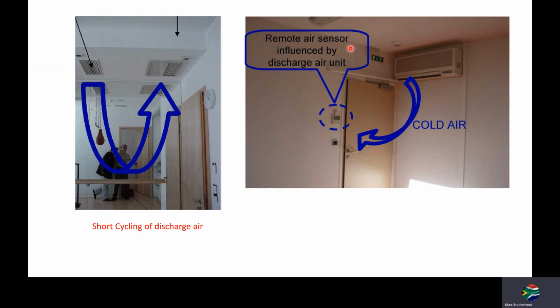Here you can see your remote sensor is virtually in line with the discharge air, so it's going to give you totally inappropriate readings. A lot of mistakes guys make as well is they install these hardwired remotes, and the sun rises in the morning and sets, and it bakes this remote, and it can go up to like 38 degrees, where it's only possibly 24 in the room. So always make sure this isn't in direct sunlight, and also make sure you're not getting the cold discharge air blowing straight on this, because your expansion valve is going to modulate on the feedback. It's going to do averaging on that sensor as well as your return air sensor, and your room isn't going to be cooled properly.